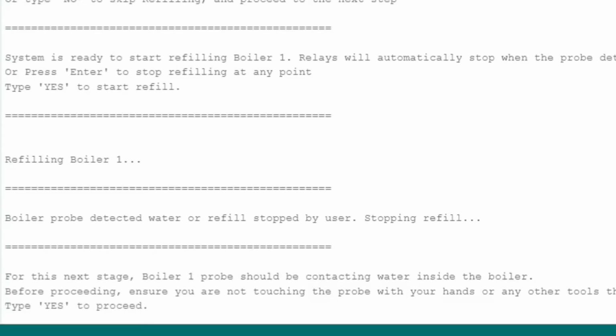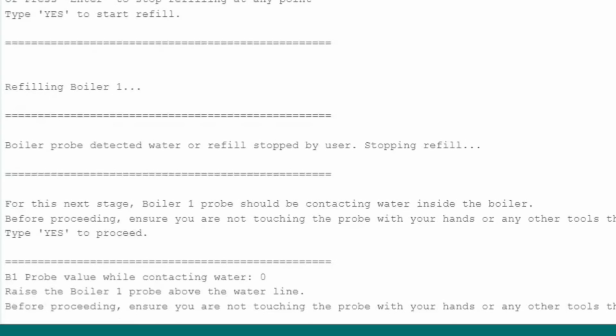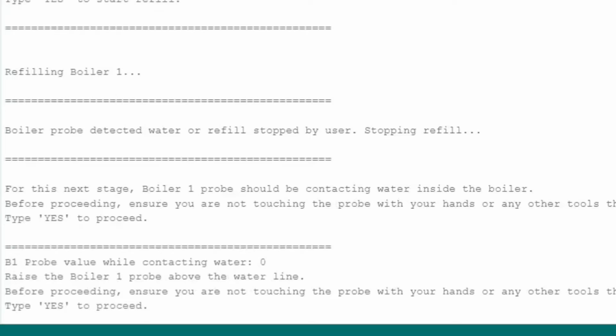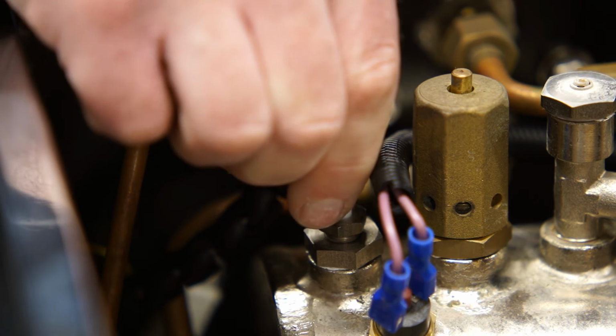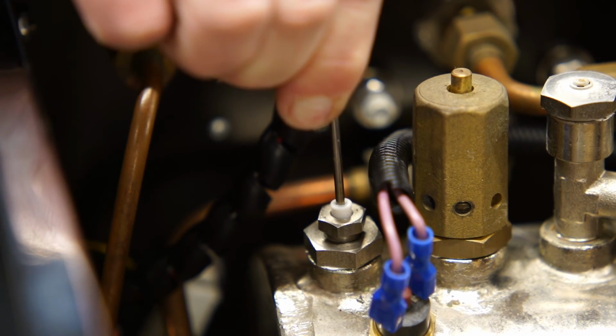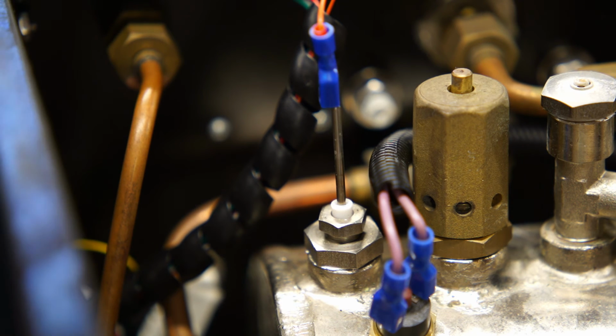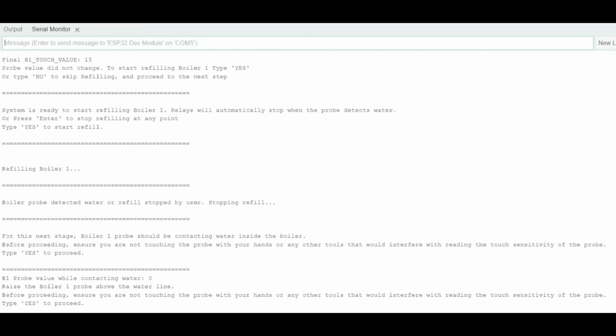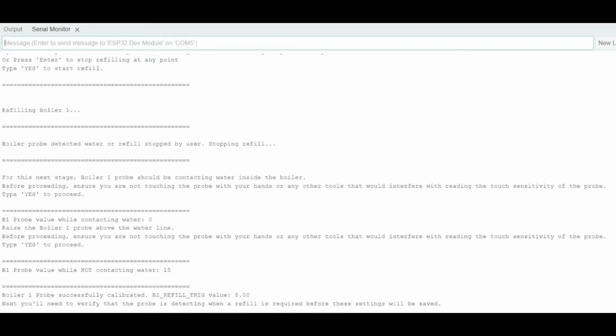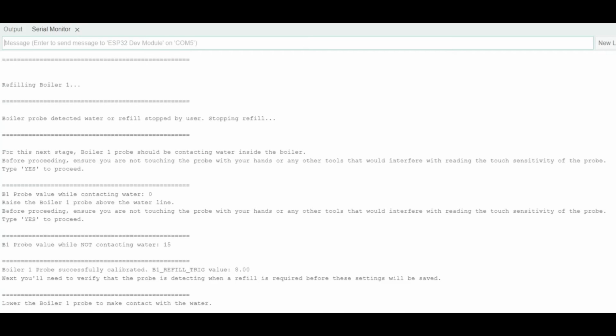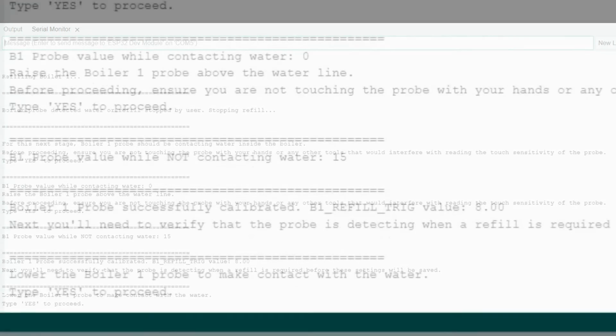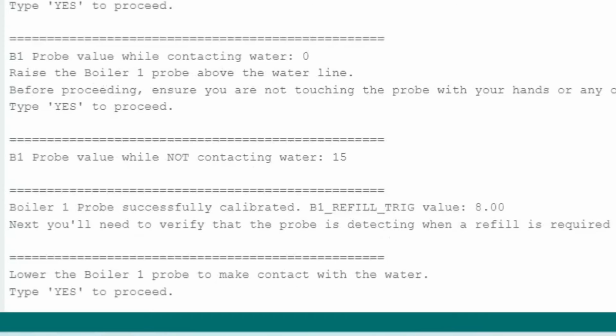Now that we have water inside the boiler, the wizard can now calibrate the probe. Next, I'm prompted to raise the probe to break contact with the water. The wizard automatically calculates the new B1 refill trigger value as 8. Before these settings are saved, the wizard wants us to verify the new setting is correctly triggering a refill.